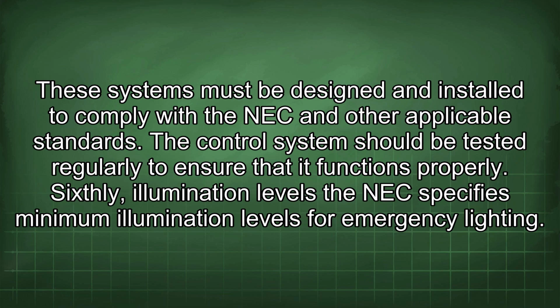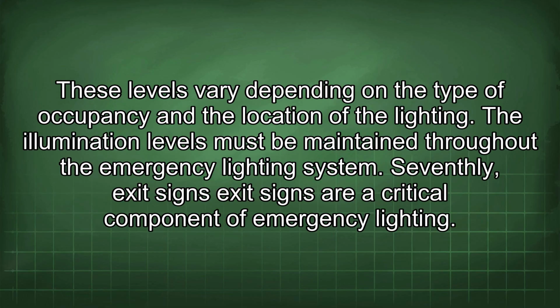Sixthly, illumination levels. The NEC specifies minimum illumination levels for emergency lighting. These levels vary depending on the type of occupancy and the location of the lighting. The illumination levels must be maintained throughout the emergency lighting system.